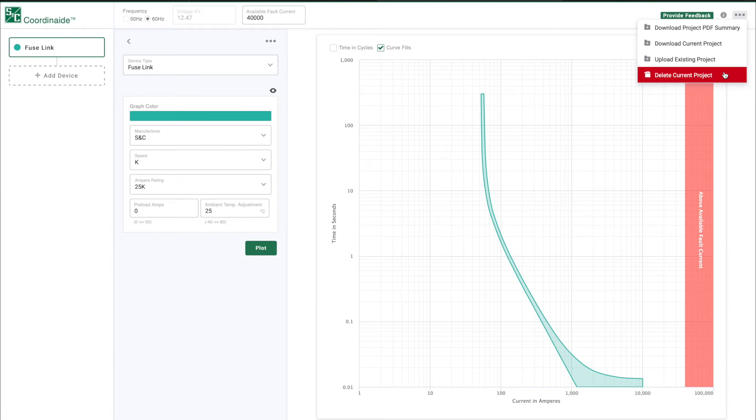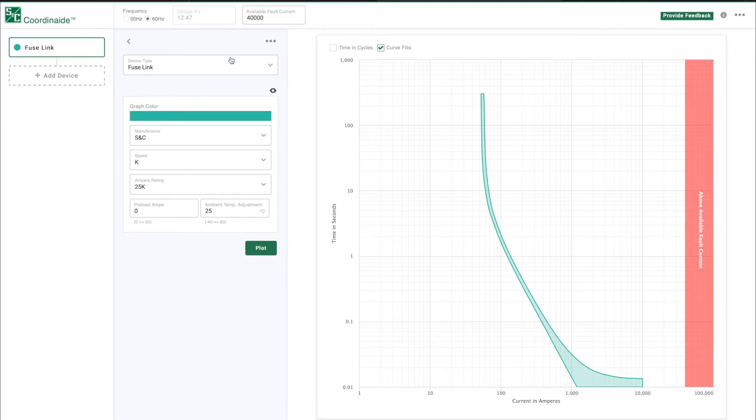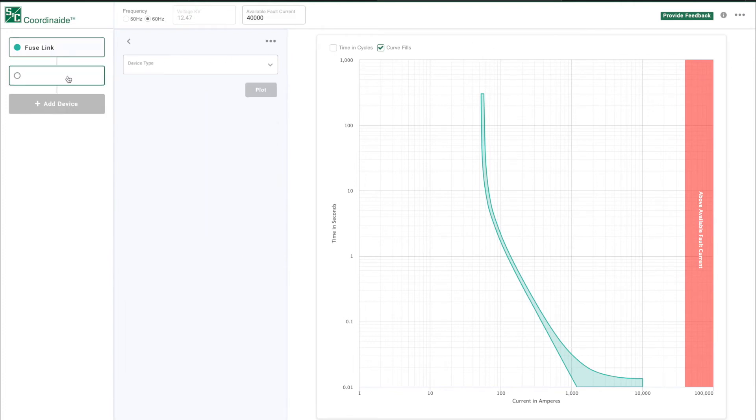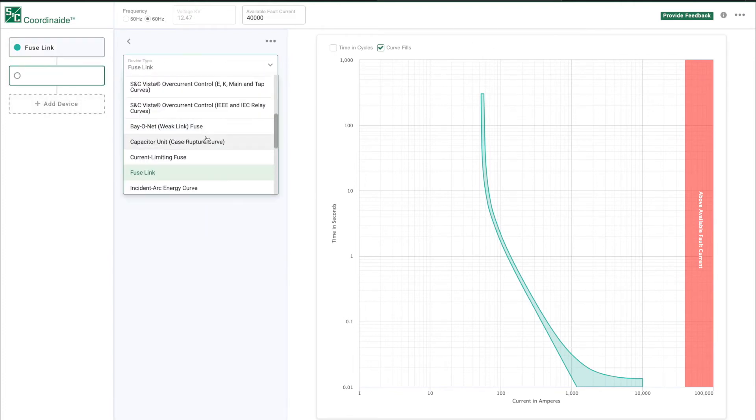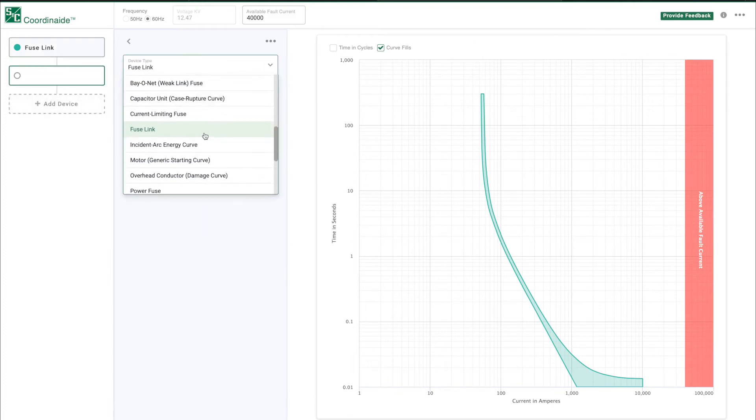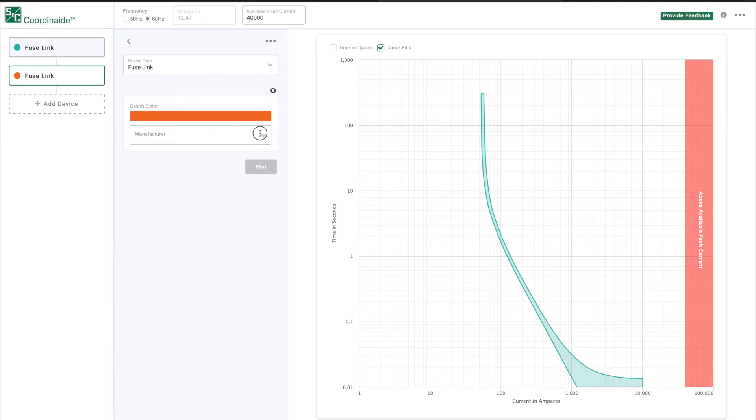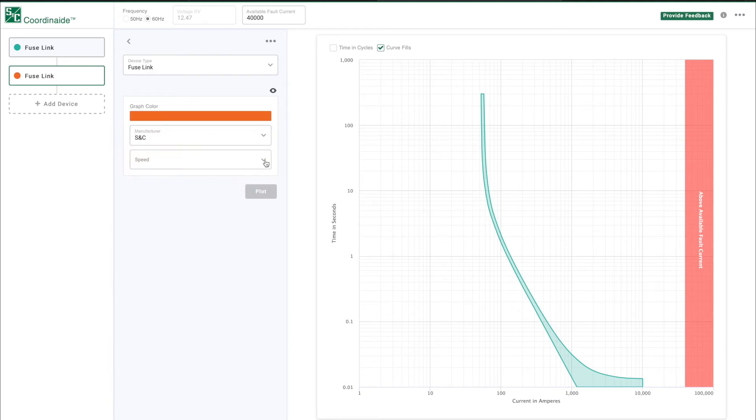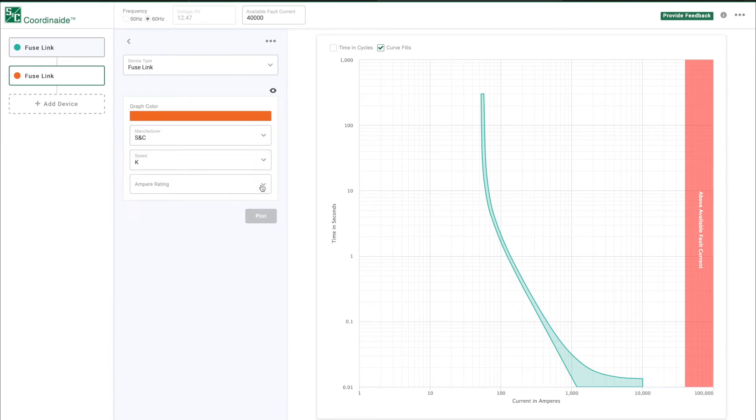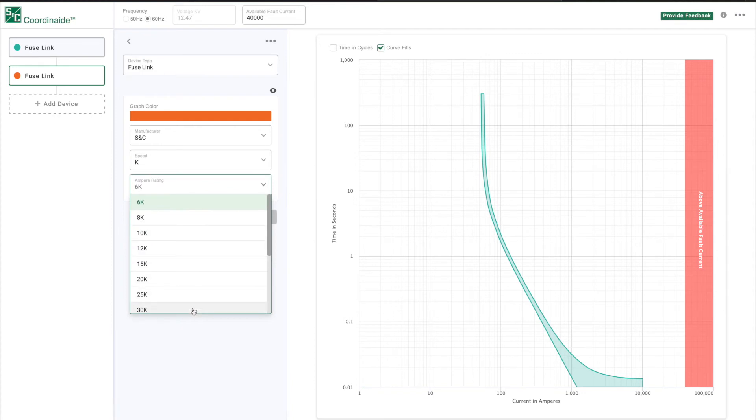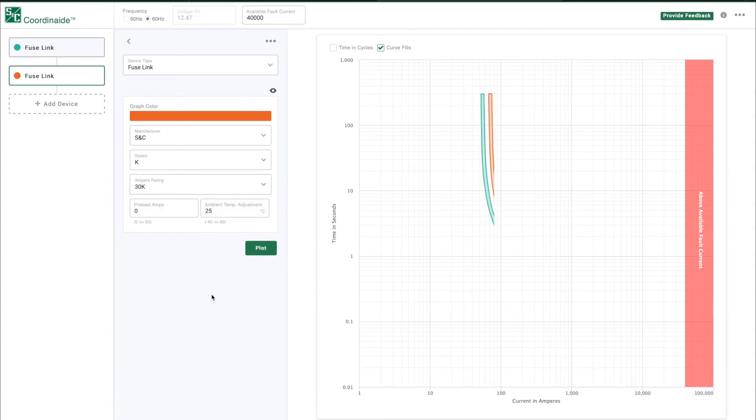It's easy to compare two fuses by simply adding a second one. Click Add Device. I'll choose another fuse link. I'll choose S&C as a manufacturer and I'll make this a 30K fuse. This will plot both fuses and allow me to make coordination decisions.